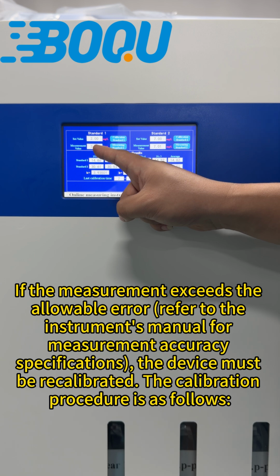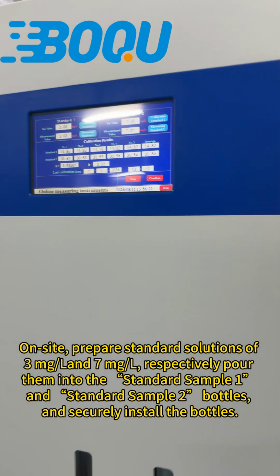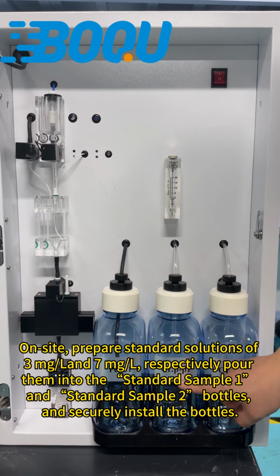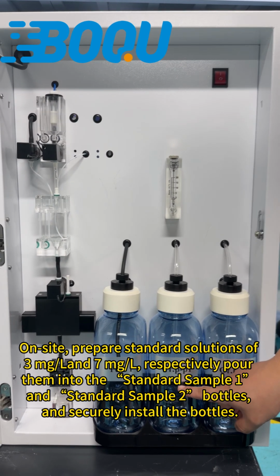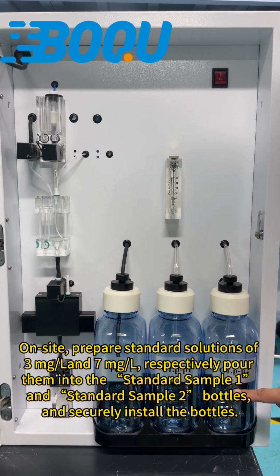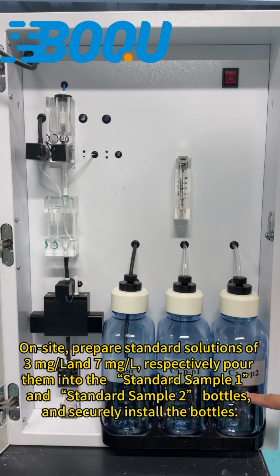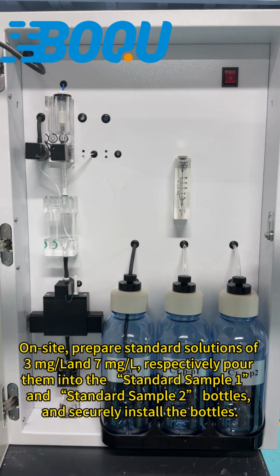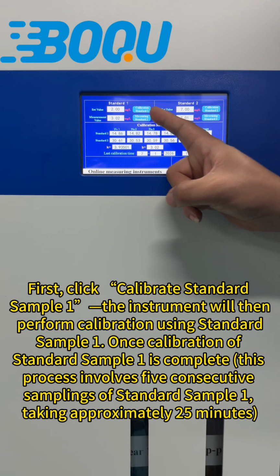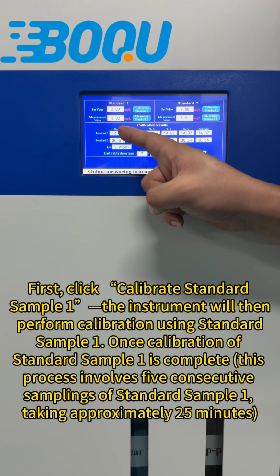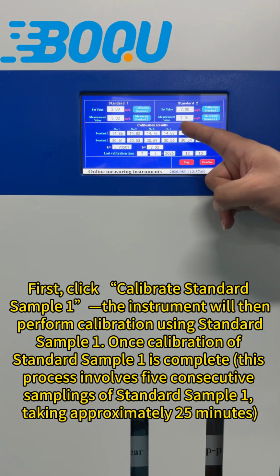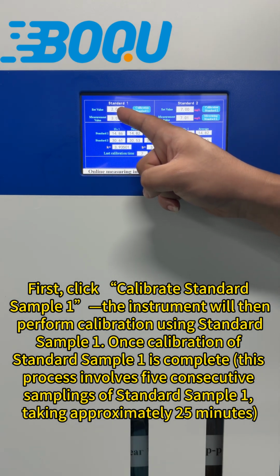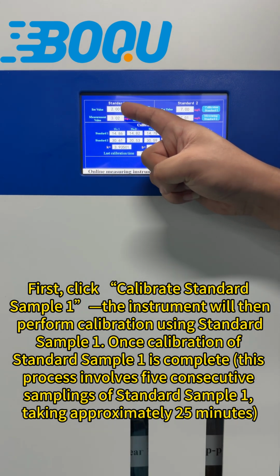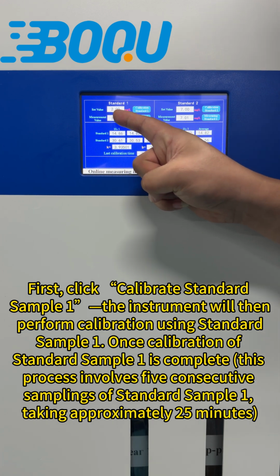The calibration procedure is as follows. On-site, prepare standard solutions of 3 mg per liter and 7 mg per liter. Respectively, pour them into the standard sample 1 and standard sample 2 bottles and securely install the bottles. First, click Calibrate Standard Sample 1. The instrument will then perform calibration using Standard Sample 1. This process involves 5 consecutive samplings of standard sample 1, taking approximately 25 minutes.